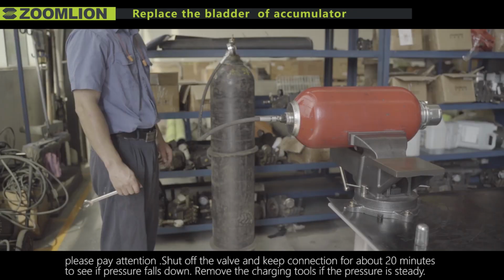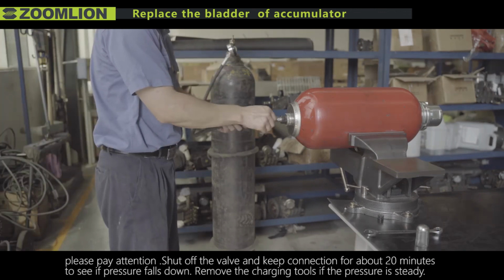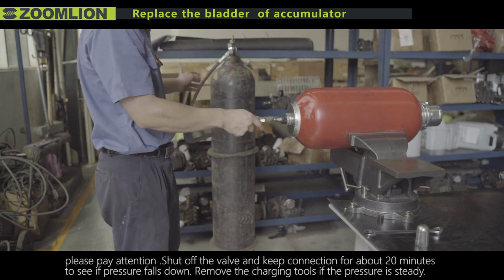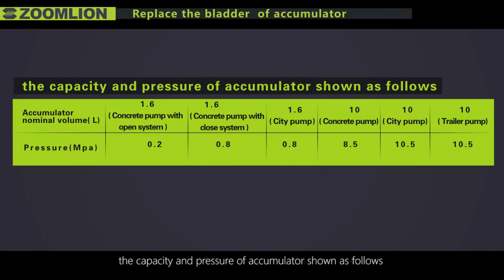Please pay attention, shut off the valve, and keep connection for about 20 minutes to see if pressure falls down. Remove the charging tools if the pressure is steady. The capacity and pressure of accumulator shown as follows.